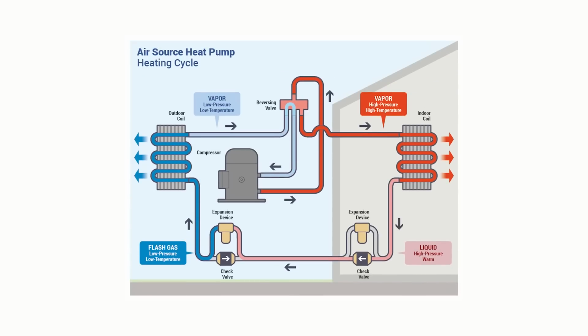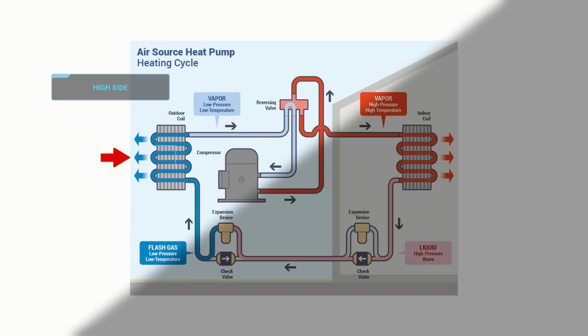Another thing that a lot of people mistake when they think about pressure testing on these is they'll say, well, high-low pressure, how does that work? Low side pressure versus high side pressure. Well, keep in mind that in this case on a heat pump, your evaporator coil is on the high side because in heat mode, both of those lines are going to be on the high side. So because of that, you can pressurize the evaporator coil and the line set to that higher pressure. Just keep in mind your only risk there is pushing back through the valves.